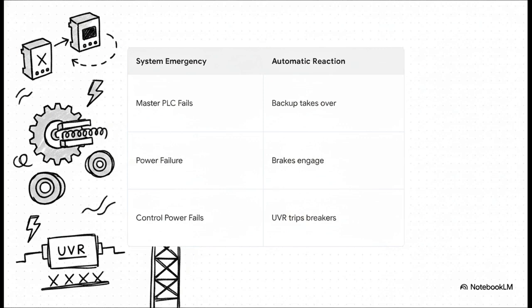process. What about a complete power failure? Well, the system doesn't just drop the rig. Instead, massive spring-applied brakes instantly catch and hold all 60 motors mechanically. And if just the control power fails, an under-voltage release automatically trips the main circuit breakers to prevent any rogue electrical anomalies from causing uncommanded movements. The rig is literally designed to fail safe automatically.